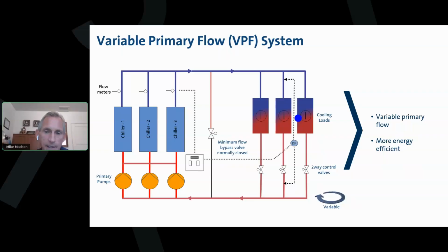Here I can see I'm actually maintaining a delta P on a zone halfway out in the system. Then we've got these control valves, and they're controlling flow through the coil, and they're also balancing the system. And these control valves waste a tremendous amount of head pressure. In a couple slides, we'll talk about something called valve authority, and we'll see these valves are using at least 50% of the head that these pumps are producing. Of course, if your load is not very big, we have a bypass here. We'll have a flow meter down here that's not shown because we need to keep the chillers happy. So we've got this bypass valve if the load is insufficient, so we can keep the chillers happy.